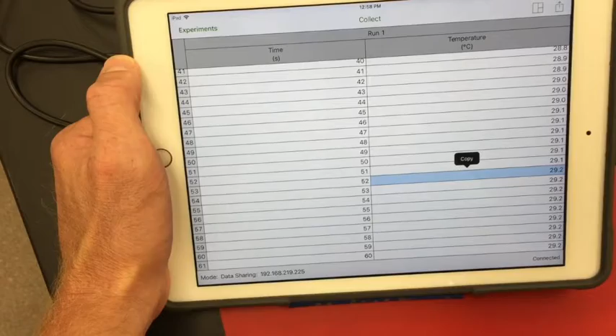Got it. Okay, method 2, go back to the app. Method 2 is to view this as a table. So upper right, click the rectangle boxes icon, go to table, and visually scan down the time at which the highest temperature was first reached. We're trying to figure out what the temperature probe's delay time is. So it looks like the time at which the highest temperature was first reached based on this is 52 seconds and 29.2 degrees Celsius. So this is your second screenshot.